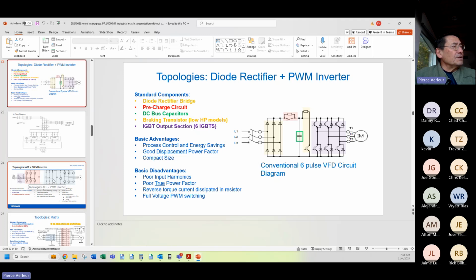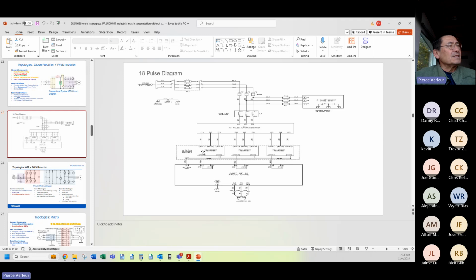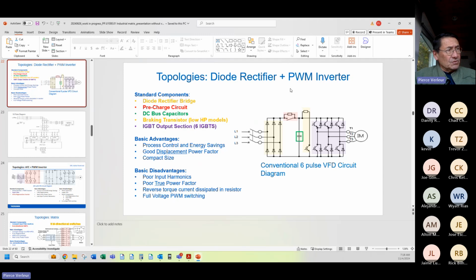And it eventually morphed into this, which is the 18 pulse. This block here represents this drive. And all this stuff in front of it, all these blocks here, are filters that are required because this drive is very disruptive to the power line and causes a lot of distortion and reduces your power factor, bad things. It was also extremely abusive to the motor and spawned the whole inverter duty motor industry, where motor manufacturers had to bulk up the motors to withstand the chop-chop waveform of the variable frequency drive. But again, back in the day, it was great. This was really fantastic technology. Not so much today.